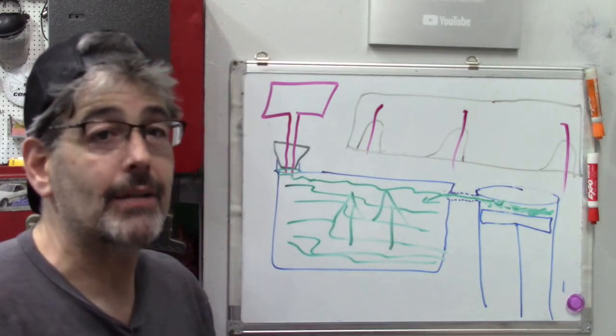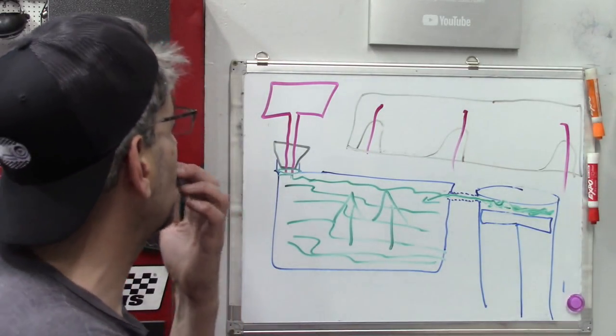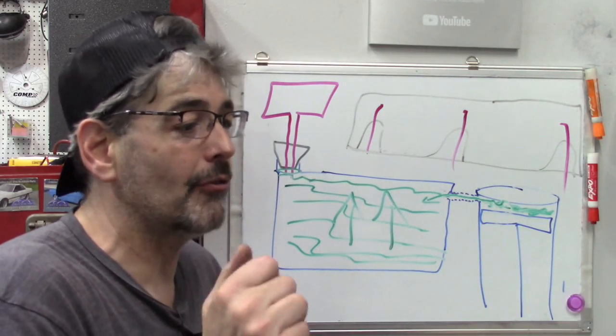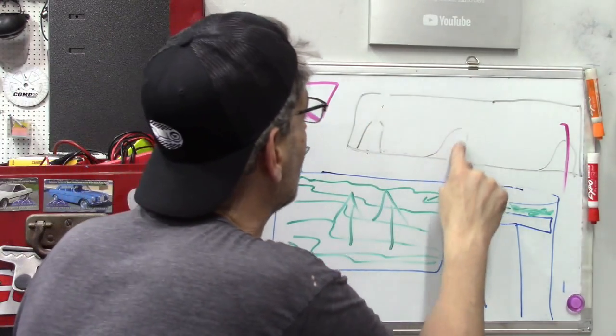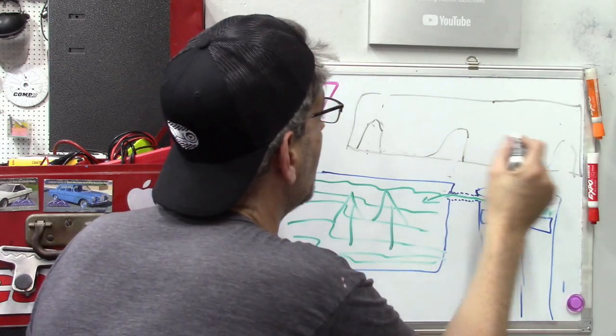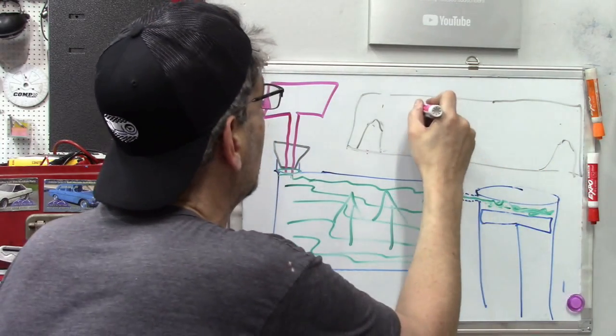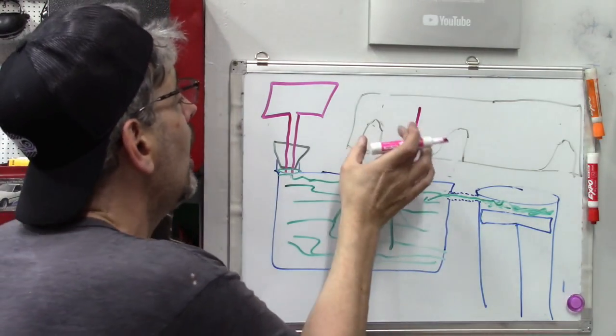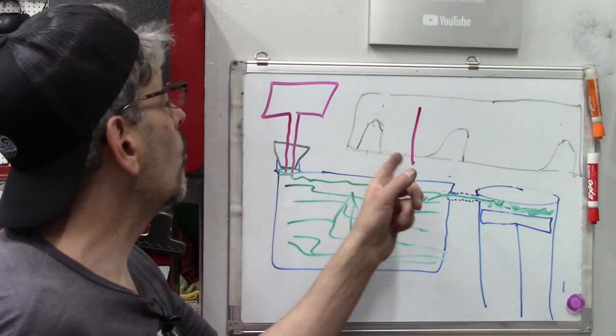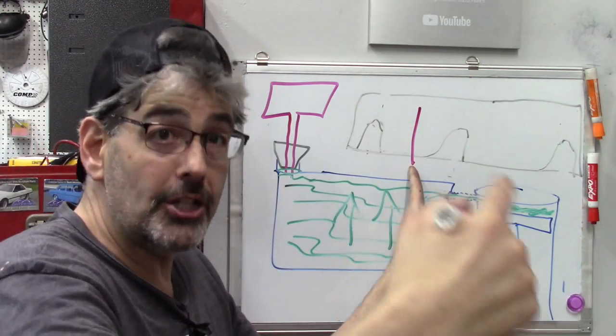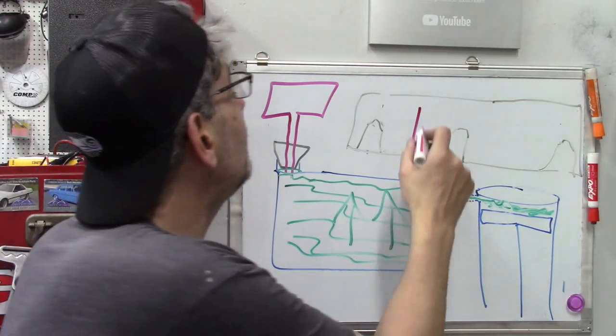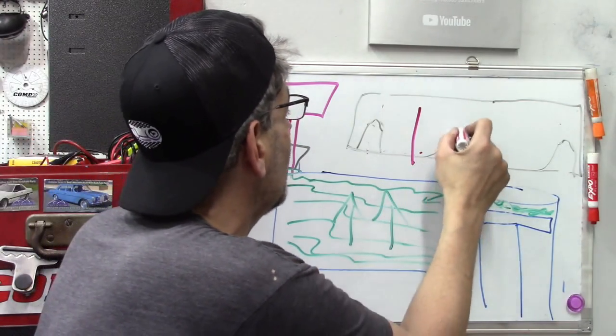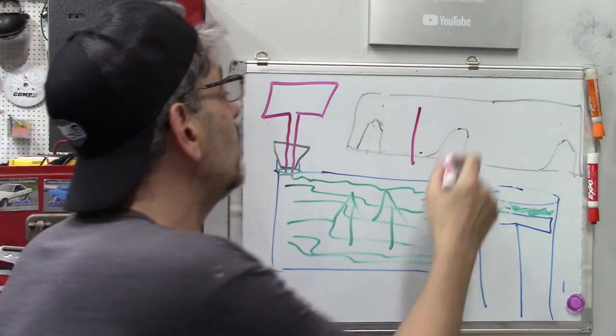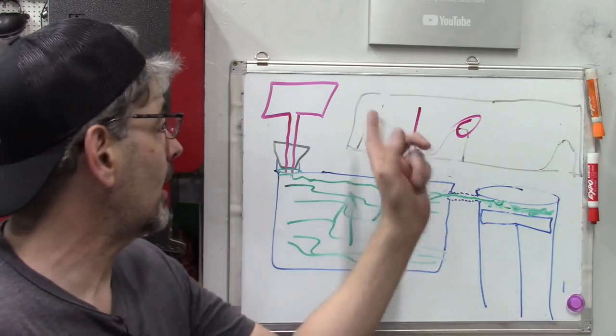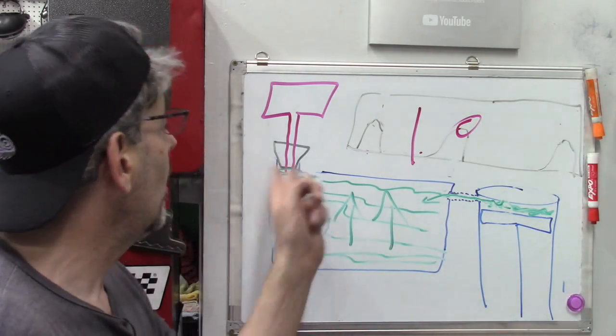We can now correlate wherever those pulses are. As a matter of fact, we don't even technically have to have the ignition pulse on that faulty cylinder, because we would still have that same rhythm of pulses. And if our signal pulse goes here, by using math to determine where that is in the crankshaft cycle, we would be able to determine that there was another cylinder event here and one here, and then going through the firing order, we would still be able to determine the number of the cylinder that correlates to those pressure pulses we see in the radiator.